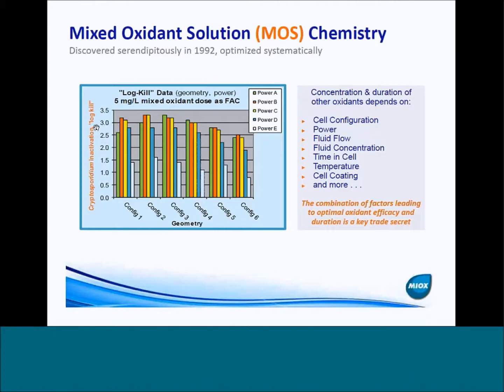If you look at this graph, on the y-axis we have cryptosporidium inactivation or log kill on a logarithmic scale, and we're getting up to about three and a half log removal. Across the x-axis there are different cell configurations. You can think of a cell configuration as being a spacing, a different electrolytic coating, internal baffling inside the electrolytic cell that causes specific flow paths, that type of thing.